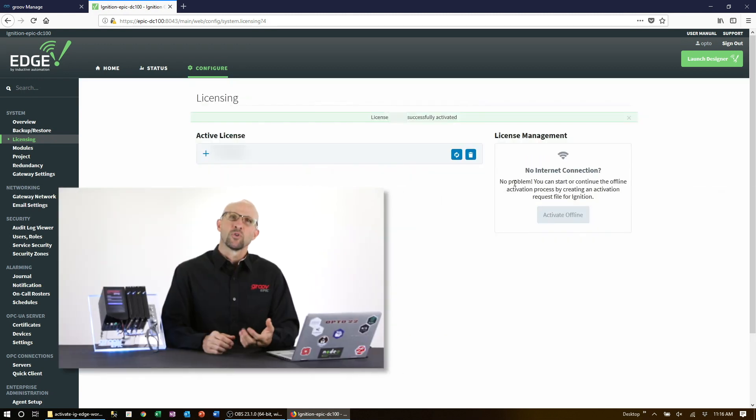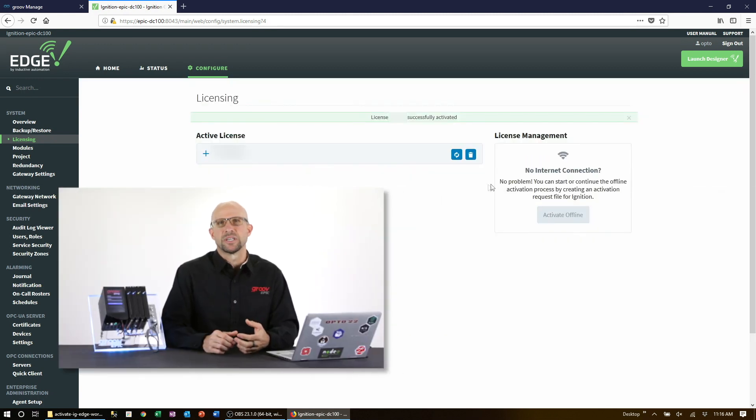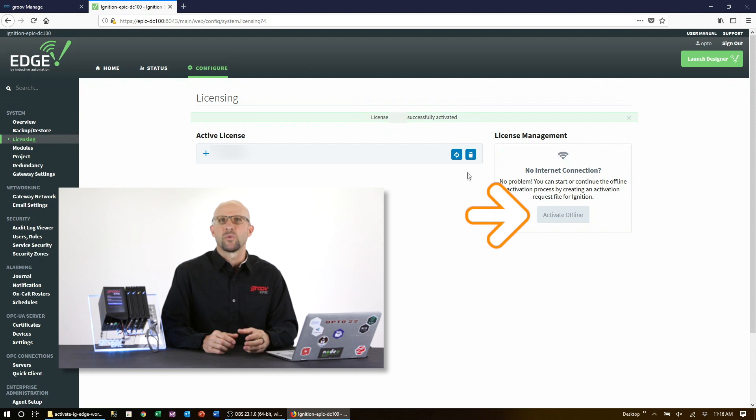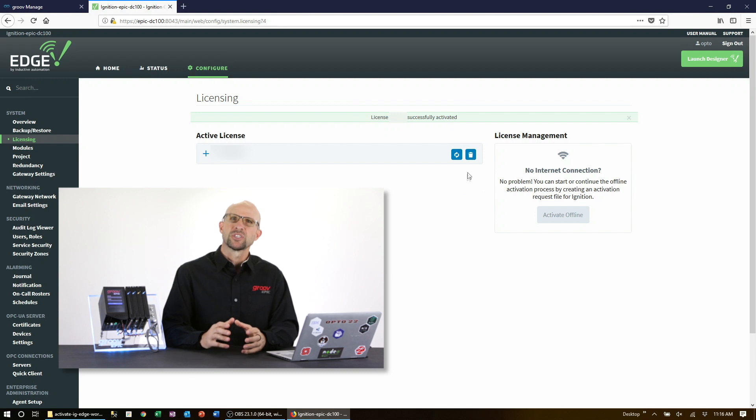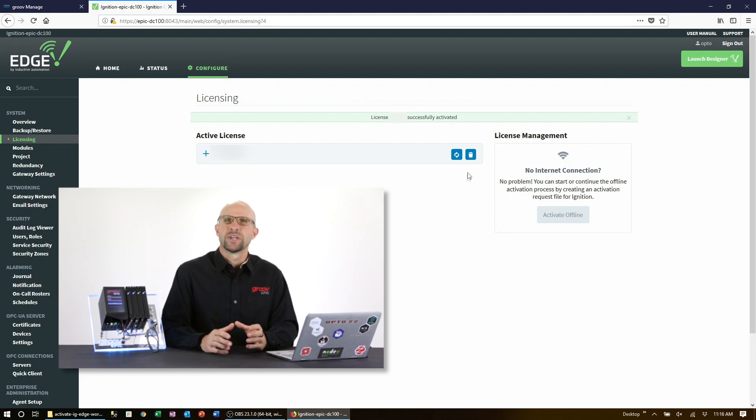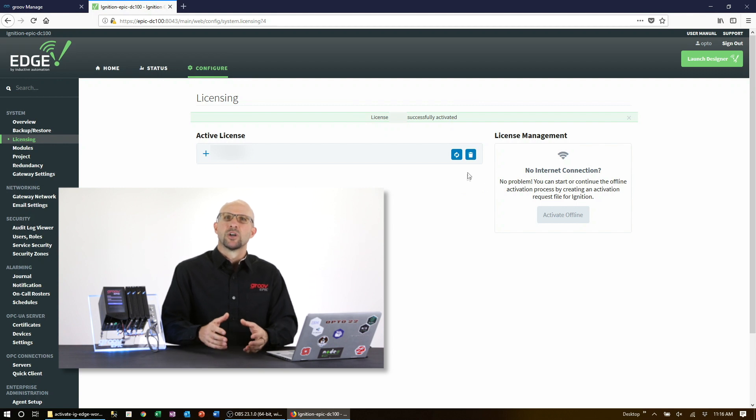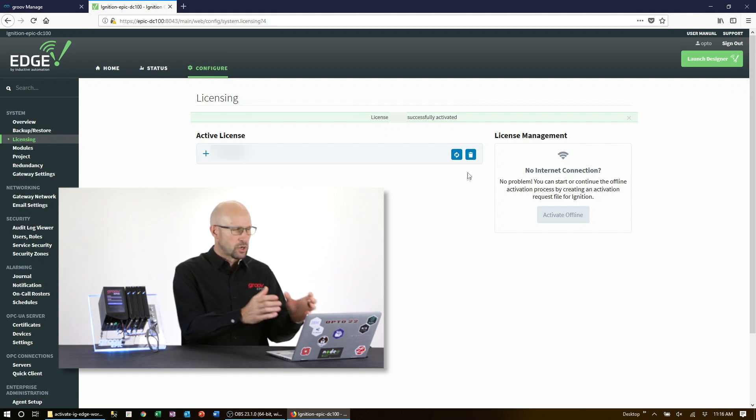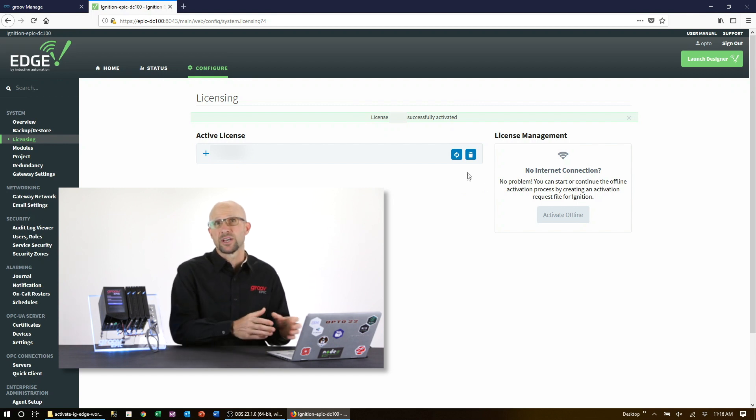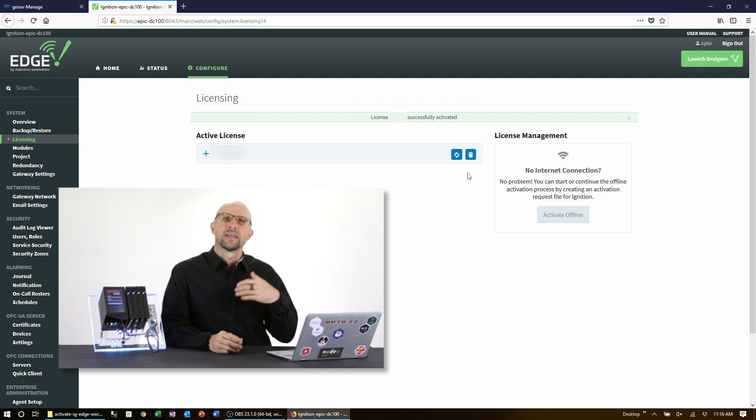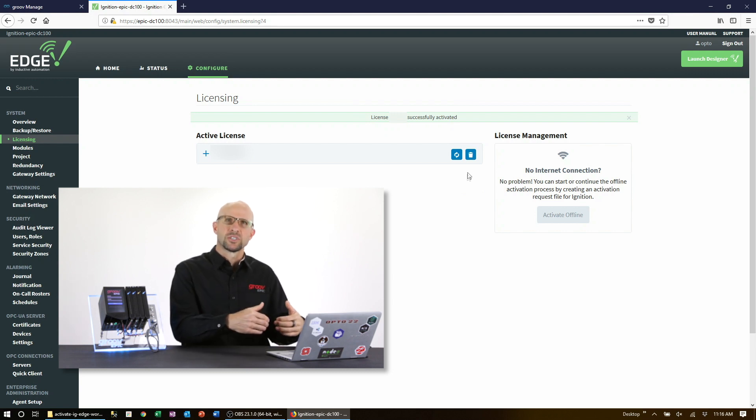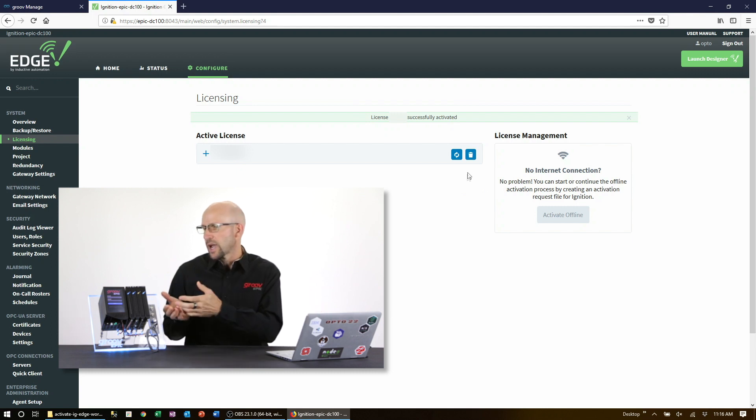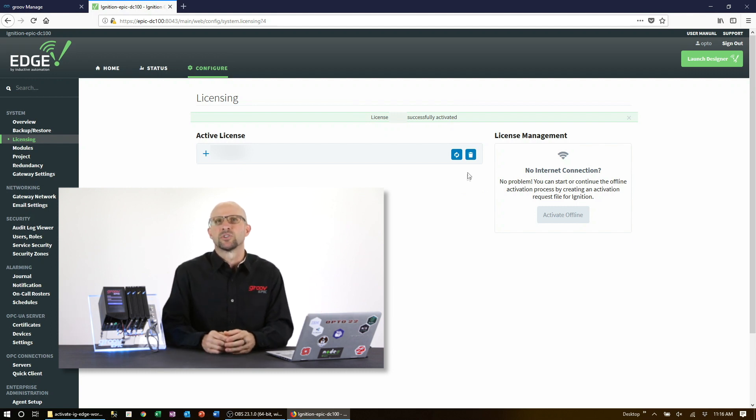If your groov EPIC doesn't have access to the internet, then click on no internet connection and follow the three steps outlined on this page. Basically, you'll need to download the offline activation request file, transfer that file to a computer that does have internet connectivity and then upload it to the URL shown. Save the returned license file onto the computer and then upload it to your groov EPIC.